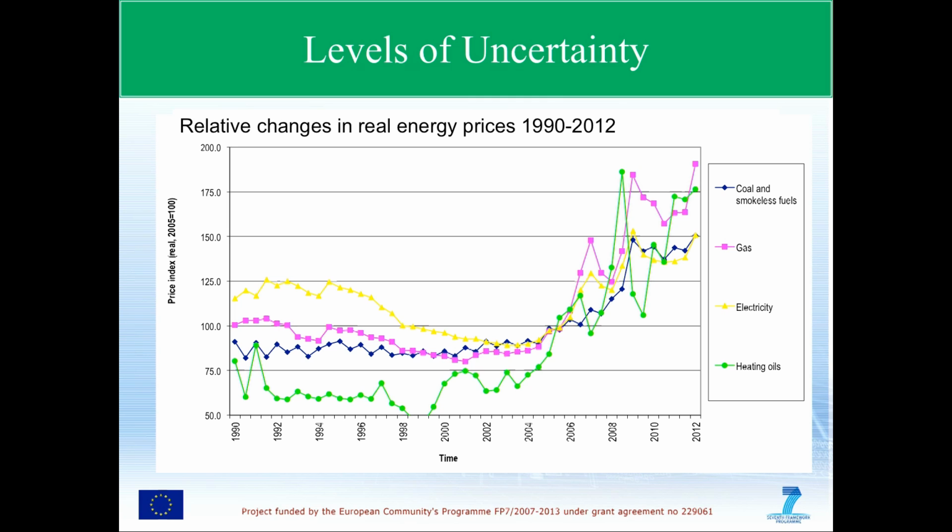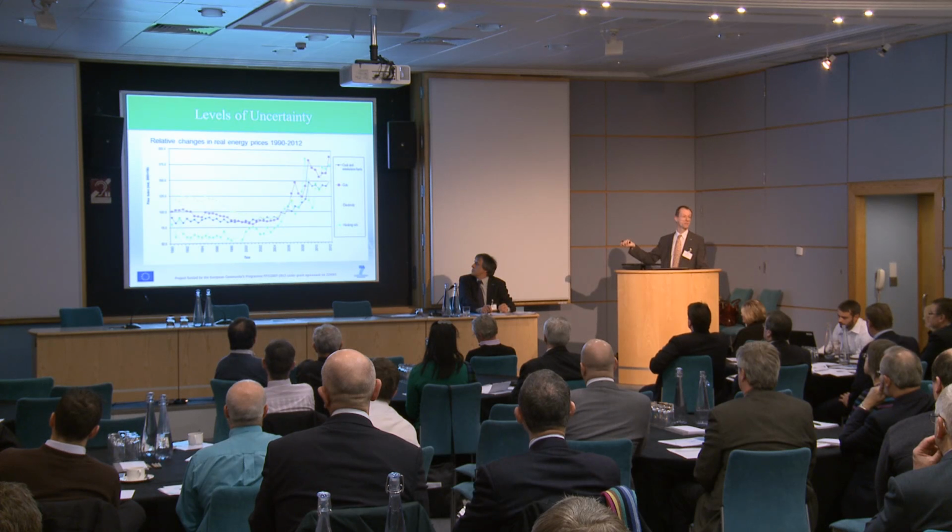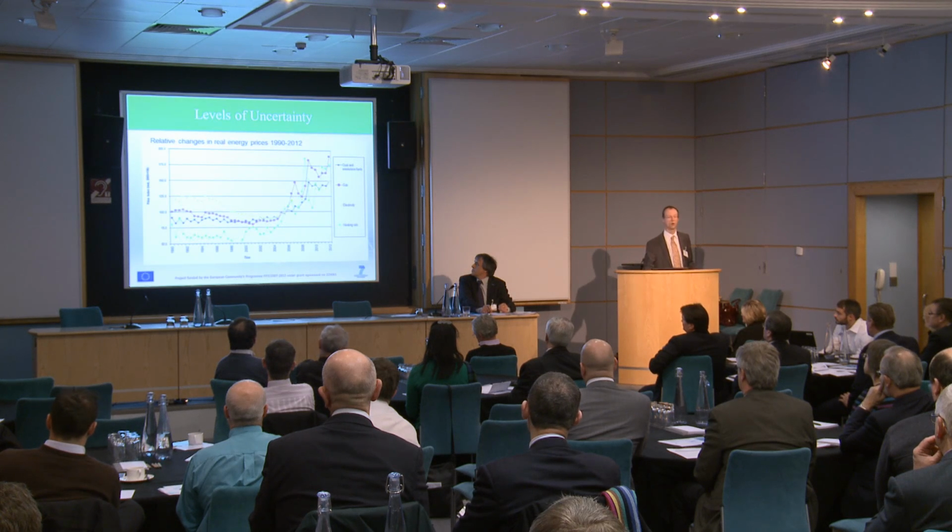If you were doing an analysis in 1995, and you had assumed that in 10 years' time your cost of gas was going to be the same, you wouldn't have been very far from the truth. If, on the other hand, you were thinking about oil, you'd have had a very different story. Although it's still got much more expensive, this is the green line now, since 2005, up by 75%. In the 10 years prior to that, it increased by about 80%. So if you're trying to compare an oil-fired heating system with a gas-fired heating system, then you need to find a way of accommodating that change in the way that energy prices move.